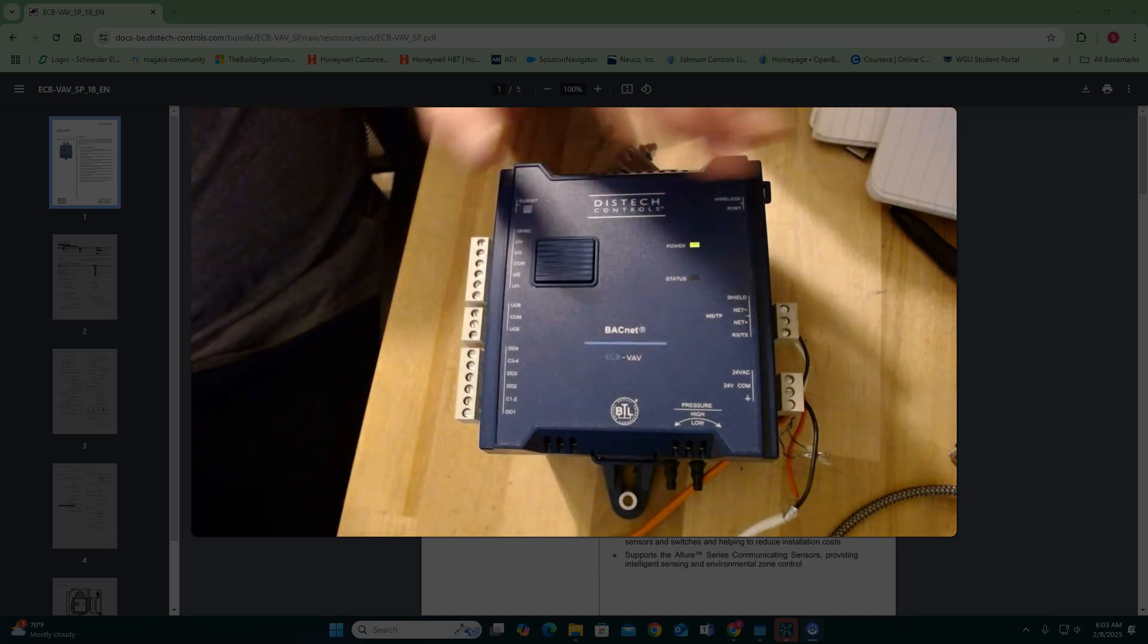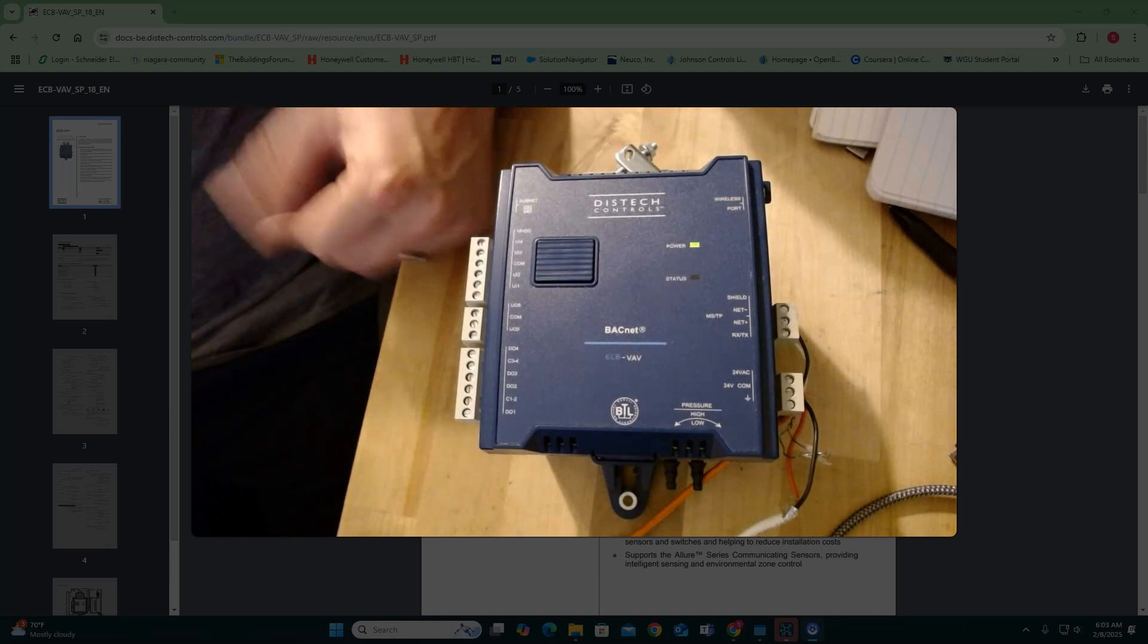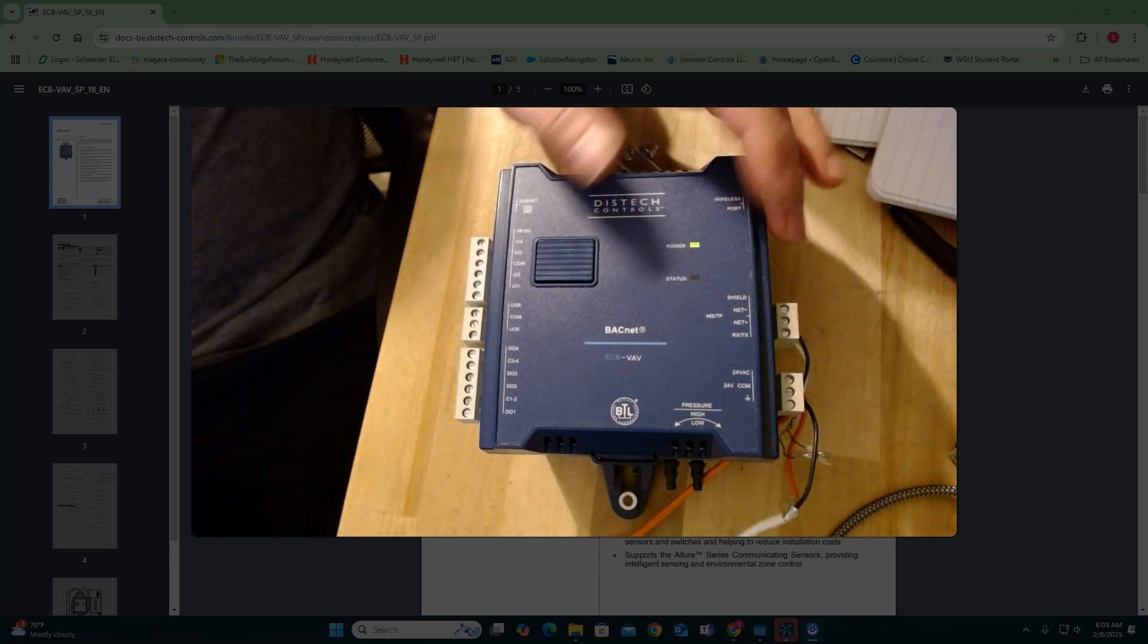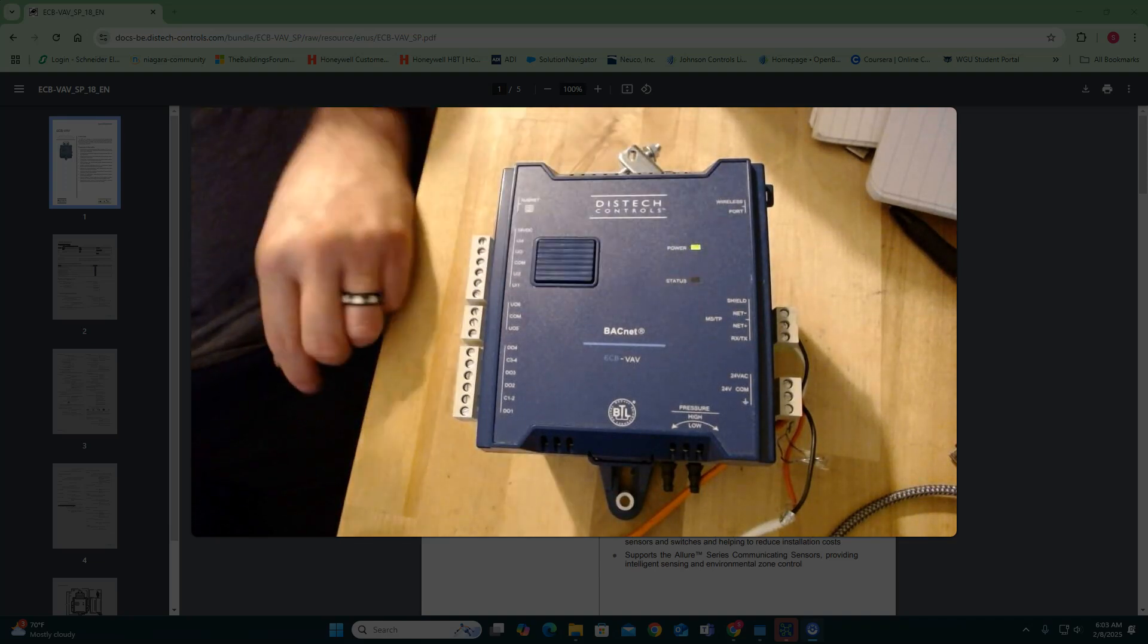So today I got a VAV controller here, ECBVAV, right? So it's BACnet MSTP. I have that hooked up to my DisTech JACE. And let's just go over some stuff. So I got four binary outputs on this controller, two analog outputs or universals, and then four universal inputs.